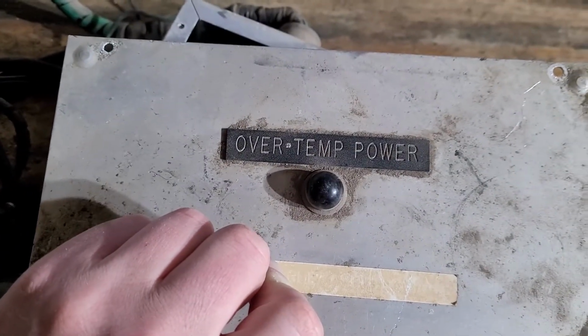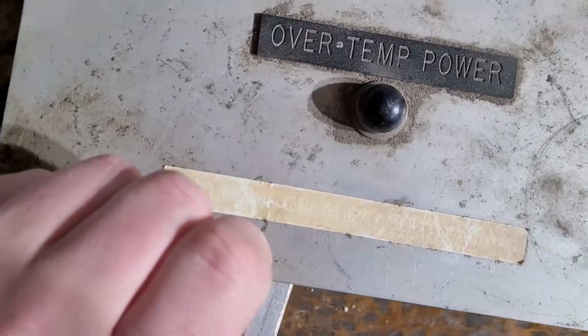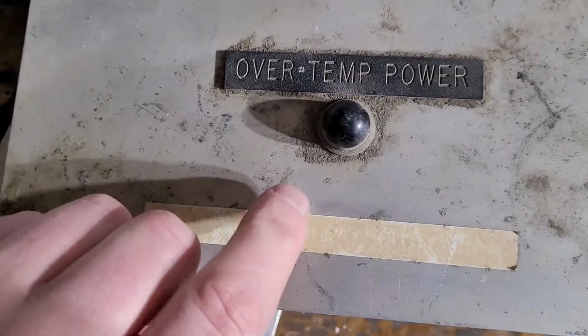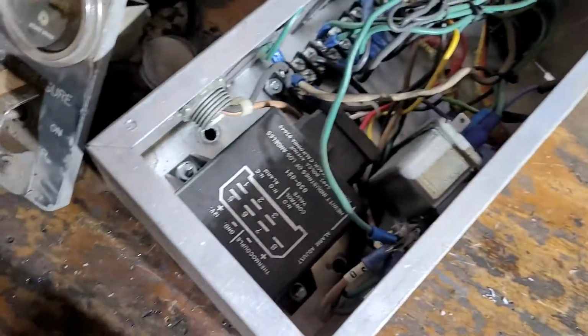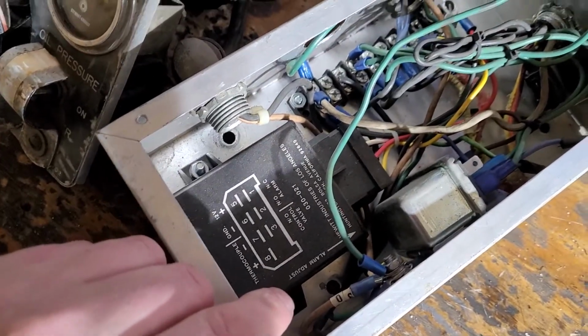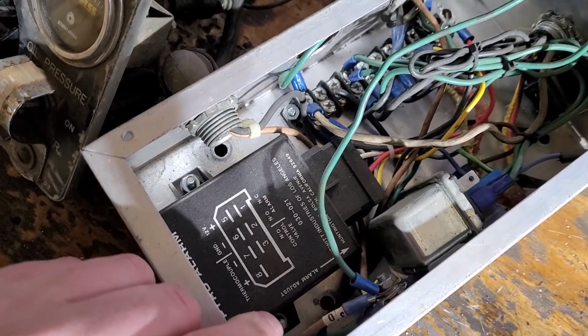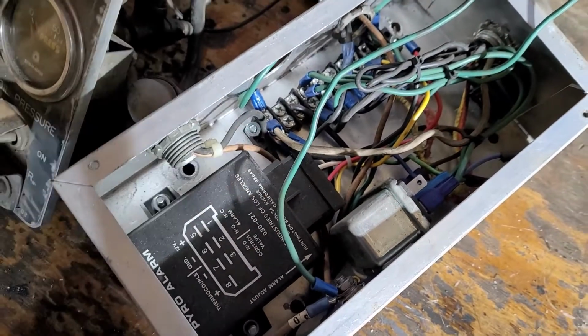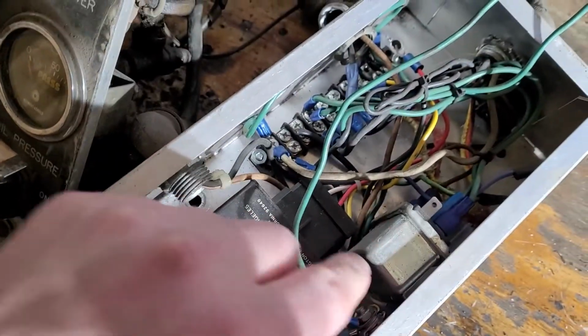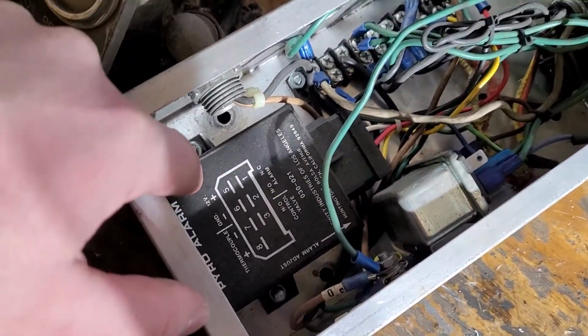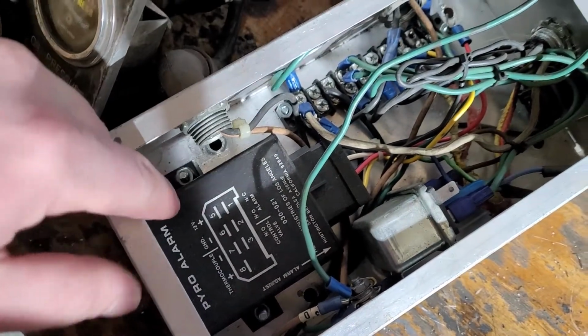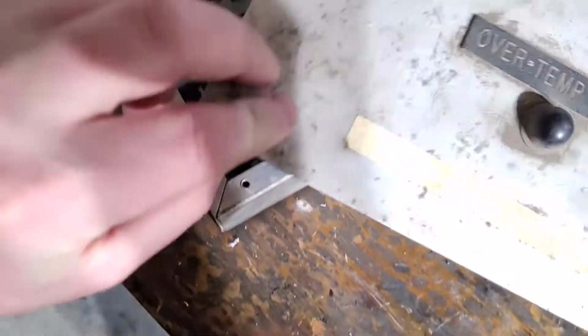On the front of this cover we've got an over temp power light and some illegible other paper tag. But I think the gist of this is it monitors the exhaust gas temperatures for over temperature, and probably automatically cuts the ignition circuit with one of these solenoids. Not exactly sure what's going on inside our pyro alarm, but we can get that sorted out.